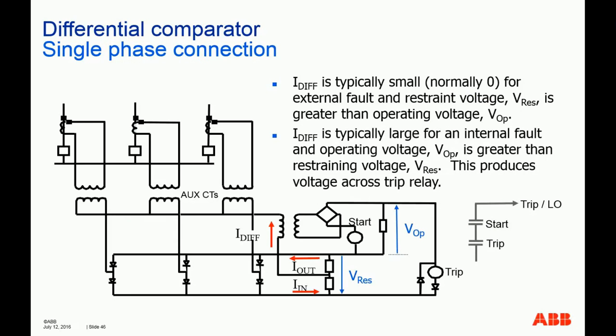Typically, the differential current is small for an external fault, and the restraint voltage is greater than the operating voltage. For an internal fault, the differential current is typically very large, of course, and the operating voltage is made greater than the restraint voltage. So this is very similar to the low impedance restraint type of differential relay that we covered earlier. Basically, you have two torques, operating torque and restraint torque, and you see which one is bigger, and it will override the other.